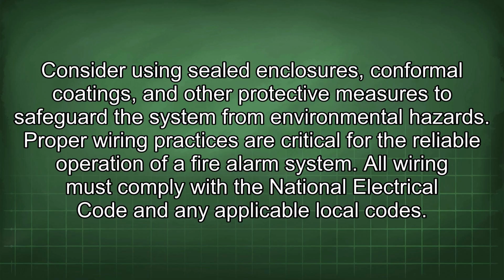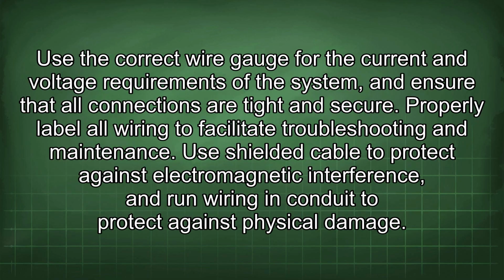Proper wiring practices are critical for the reliable operation of a fire alarm system. All wiring must comply with the National Electrical Code and any applicable local codes. Use the correct wire gauge for the current and voltage requirements of the system, and ensure that all connections are tight and secure. Properly label all wiring to facilitate troubleshooting and maintenance. Use shielded cable to protect against electromagnetic interference, and run wiring in conduit to protect against physical damage.